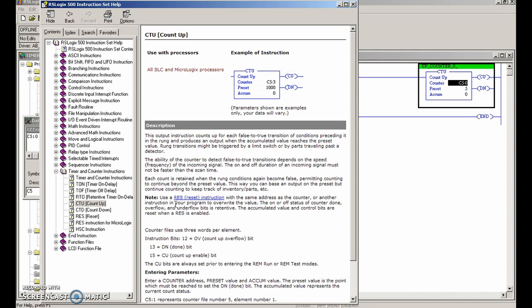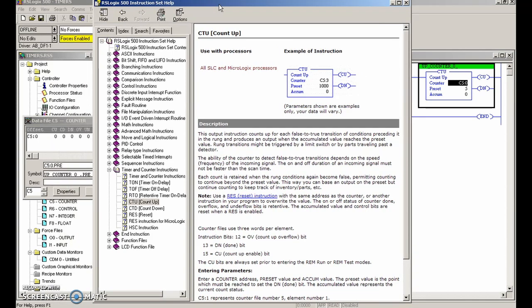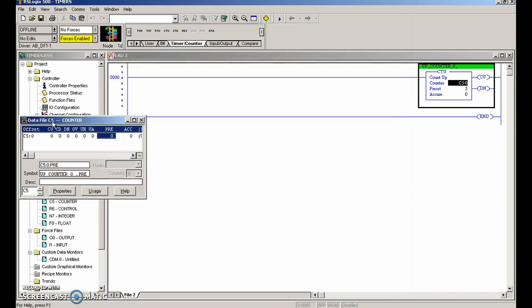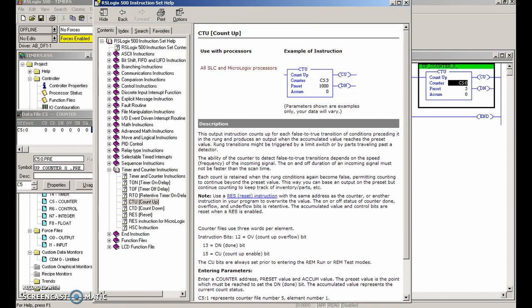We're going to have to make use of a reset in our program. Looking at the OV - it's the overflow. The overflow bit is true when the counter counts past its maximum value, which is 32,767. Once it goes past 32,767, on the next count the counter will wrap around to negative 32,768 and continue counting from there towards zero on successive false-to-true transitions.